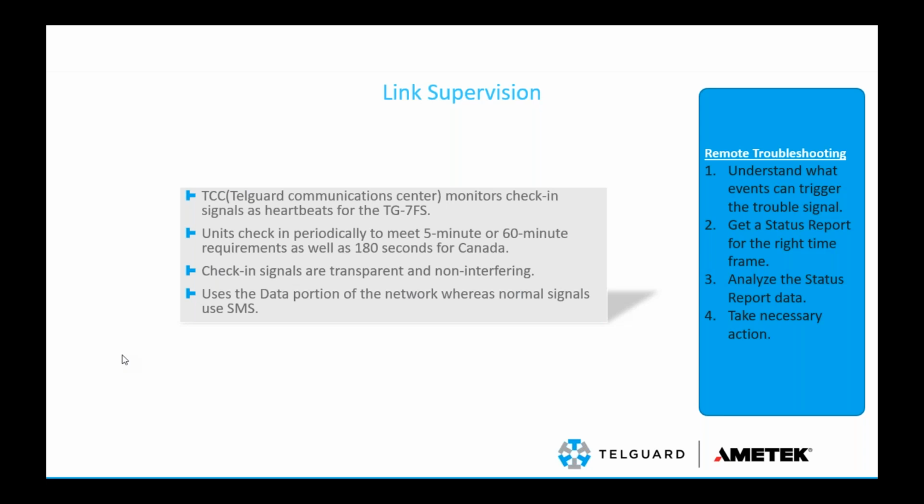Now, it's very important that you understand these check-in signals are transparent and non-interfering. What this means is, if you have a fire alarm, that alarm is still going to deliver even if we're actively checking in with the unit as the alarm occurs. They can actually happen simultaneously, but if we have to choose between the two, the alarm signal will always be what gets sent through first. Again, it shouldn't interfere.